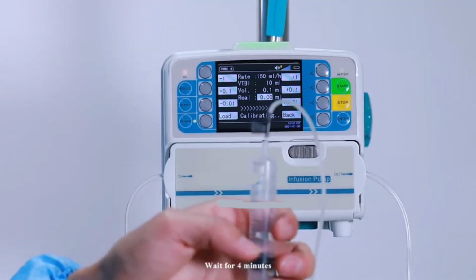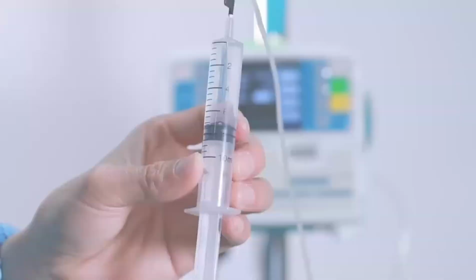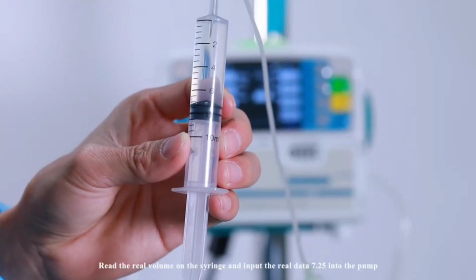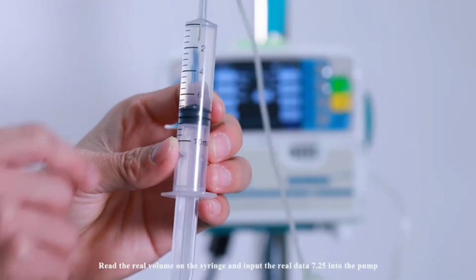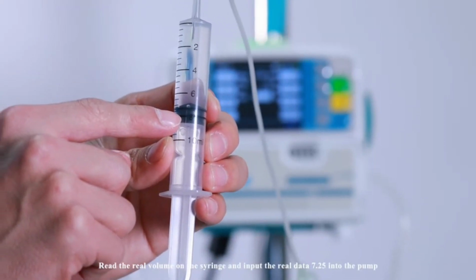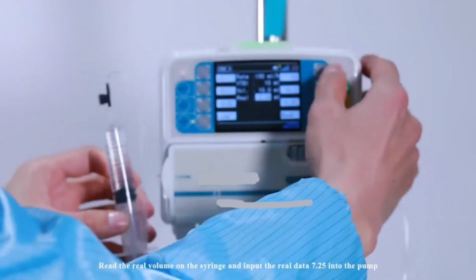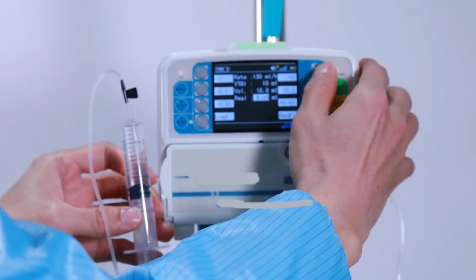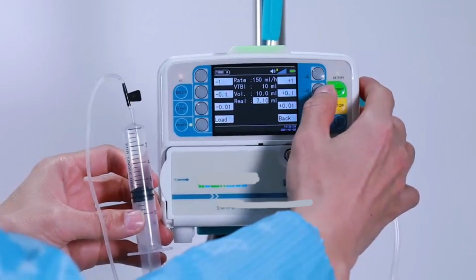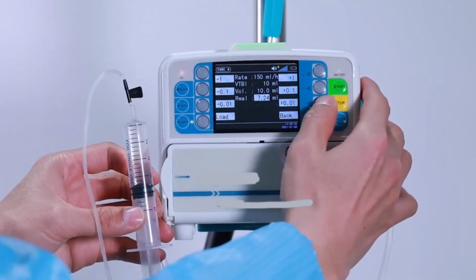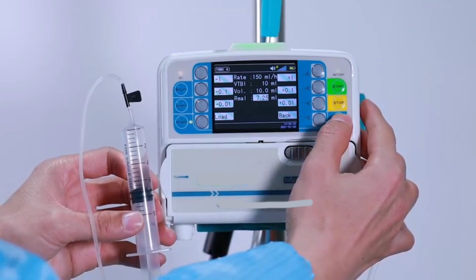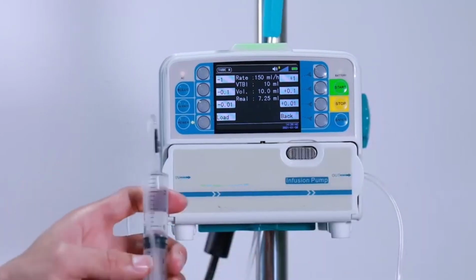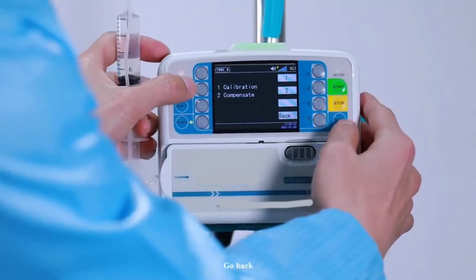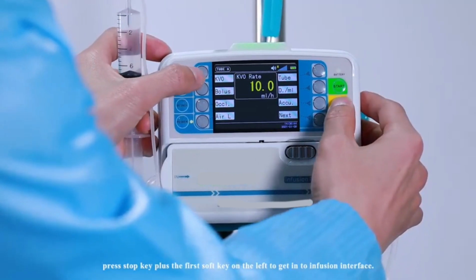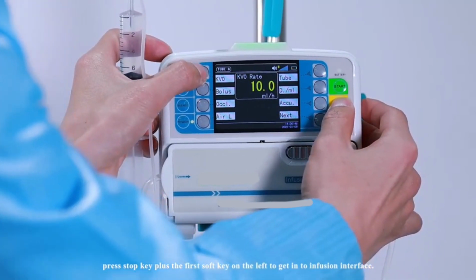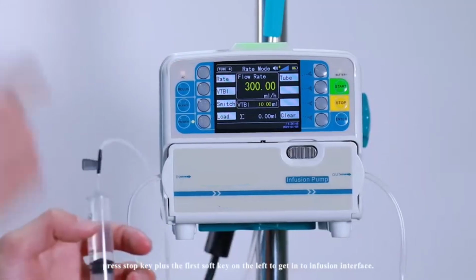Wait for 4 minutes. Read the real volume on the syringe and input the real data, 7.25, into the pump. And press enter. Go back. Press the Stop key plus the first soft key on the left to get into the infusion interface.